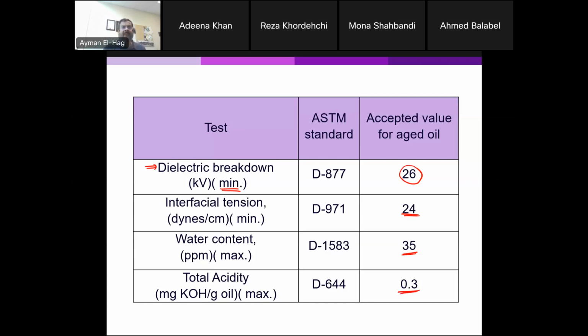Now, as I said, the oil is a reflection of the health condition of the transformer insulating system, so different actions can be taken. Sometimes you recycle the oil, if it really starts to become close to these values, or sometimes you need to change the whole oil and bring new oil. Going back to the blood example, you can add more blood to the human body, or you can take the blood, take the poisonous material out of it, and sort of filter the blood if there is a lot of poison residual in the human blood. Same thing we do here for the transformer.